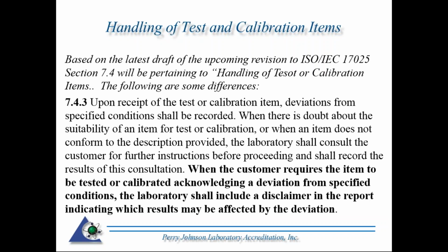So upon receipt of the test or calibration items, deviations from specified conditions shall be recorded. When there is doubt about the suitability of an item for test or calibration, or when an item does not conform to the descriptions provided, the laboratory shall consult the customer for further instruction before proceeding and shall record results of this consultation. Sort of went over that, still intact. However, when the customer requires the item to be tested or calibrated, acknowledging a deviation from specified condition, the laboratory shall include a disclaimer in the report indicating which results may have been affected by the deviation.